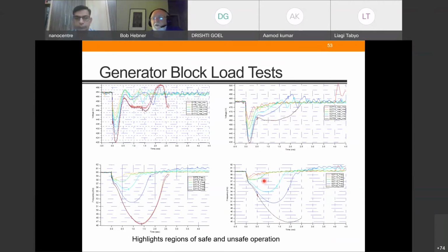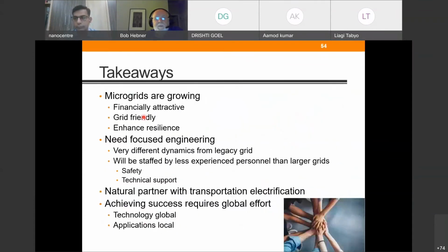We also tried some generator block load tests, which means just dumping a load on a generator. We couldn't get anything profound out of it because the generators all had their own governors and control systems, and since they were rented, they wouldn't let us take them off to see if we could break them. So we just measured the control systems they had, nothing very profound. But that's another thing to consider when looking at the stability of a microgrid.